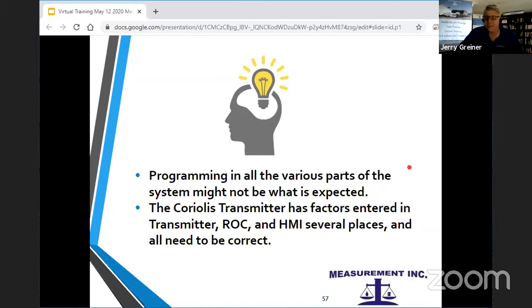Your Coriolis transmitter has factors entered in several places, and here it's in a transmitter, in a ROC, in an HMI, and they all need to be correct so that it works. So the transmitters need to have the right factor in the different places. And anyhow, this one had it in 3 different places, and it didn't use a normal setup.